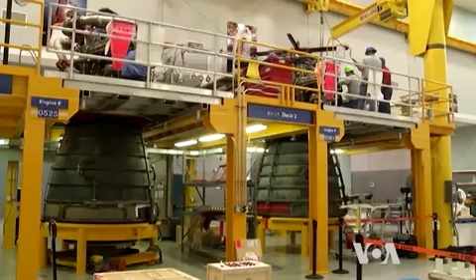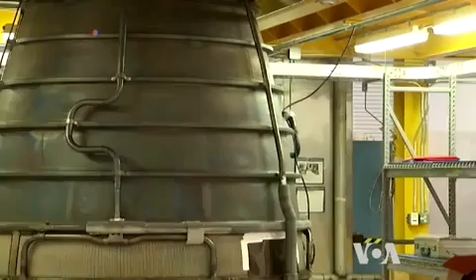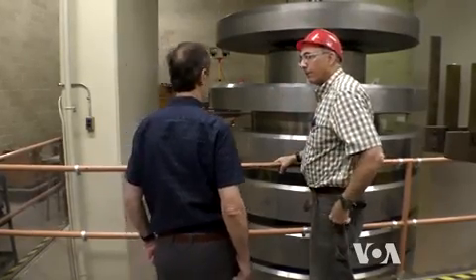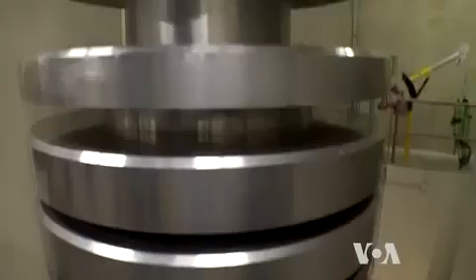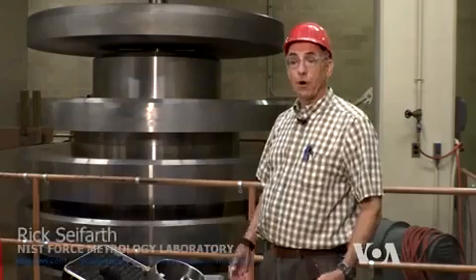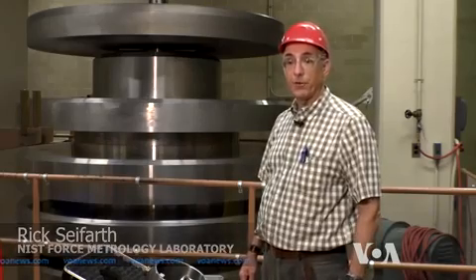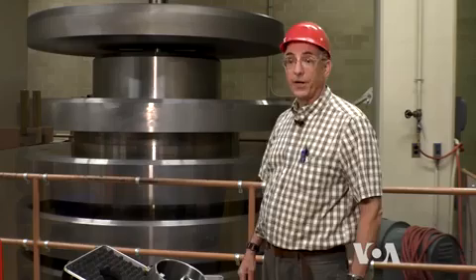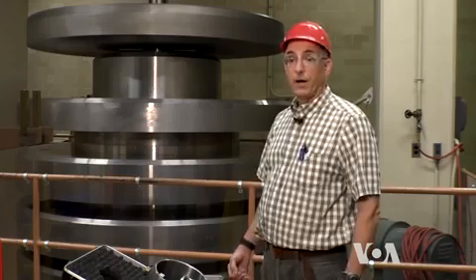Many private and government laboratories have instruments for measuring large forces, but in order to read those forces correctly, they have to be calibrated. In the U.S., that is done at the National Institute of Standards and Technology with a huge stack of dead weights, themselves calibrated to a very precise weight. Through the art and procedure of calibration work, the standard forces are placed upon a unit under test, and the owner of the device receives the output from his device under that particular applied force.